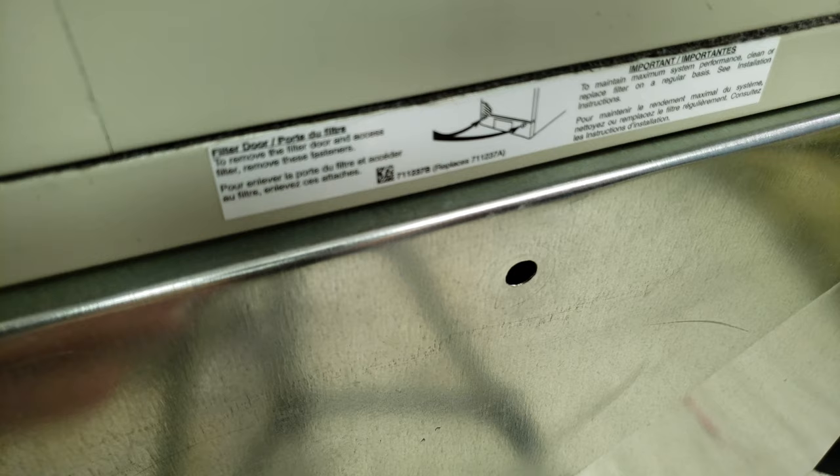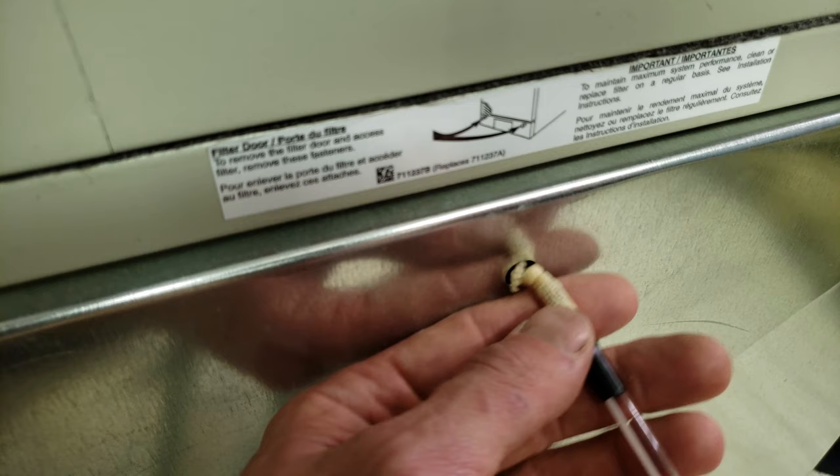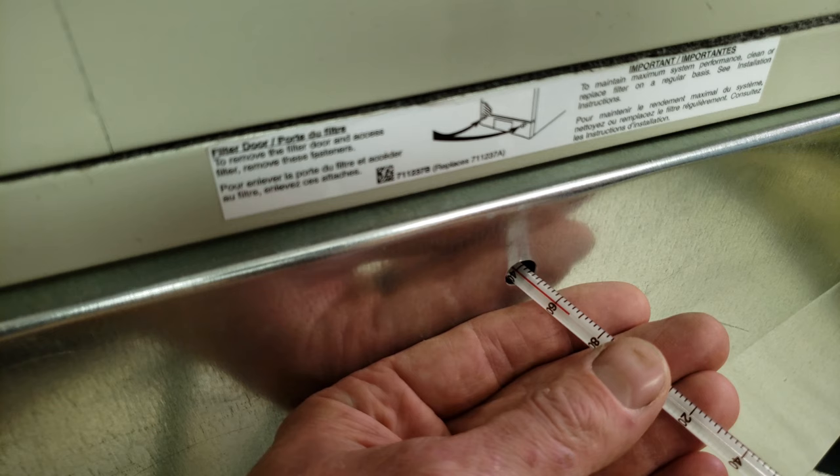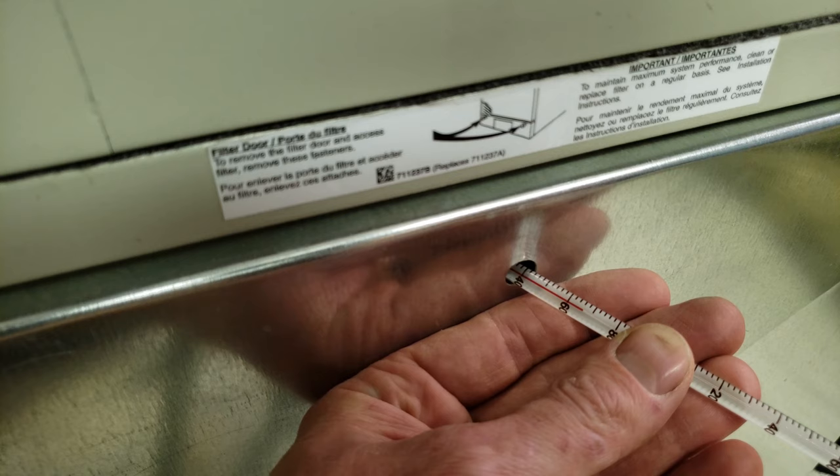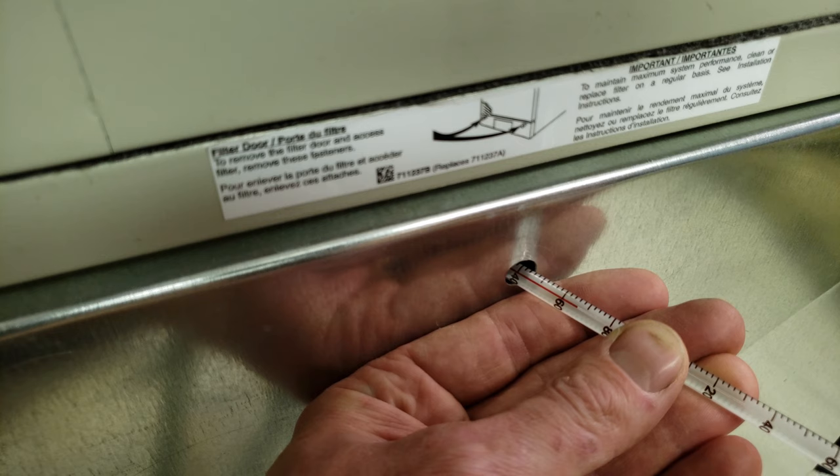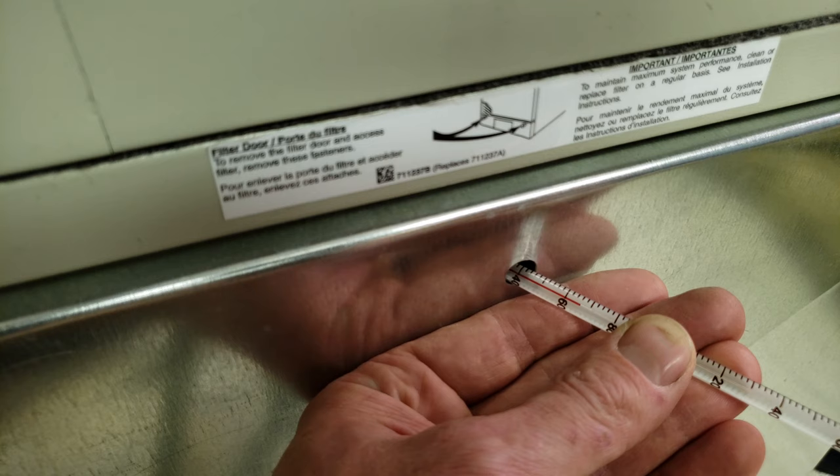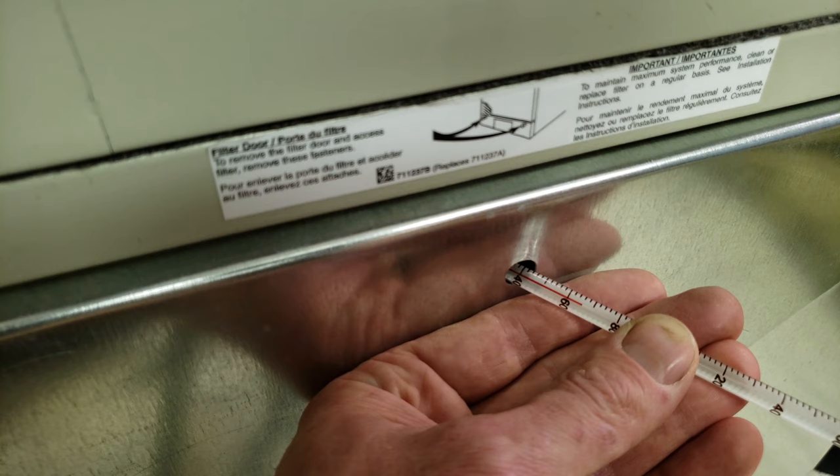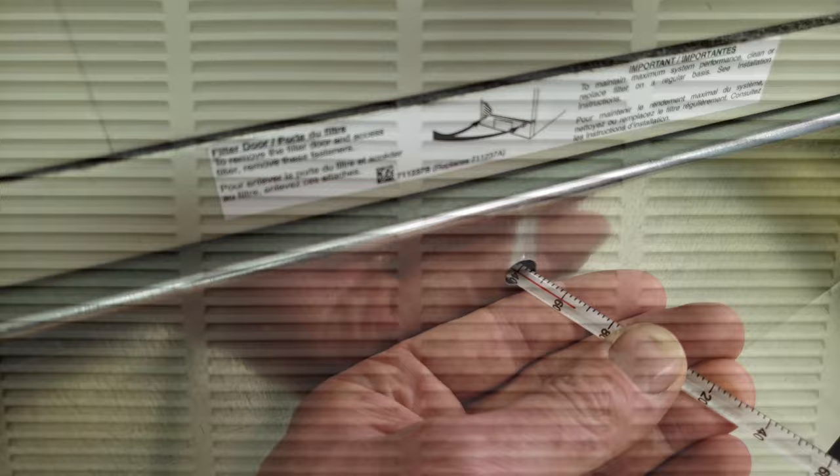Now we're at our air handler, and we have our evaporator coil here, our filter here, and here's the return. We have our thermometer with our wet sock, and we're just going to insert this and see what our wet bulb temperature is. We've got to give this a little bit of time, although I did just have this in this return here beforehand. We're reading right about 66 it looks like, but you would want to keep that in there for about two minutes.